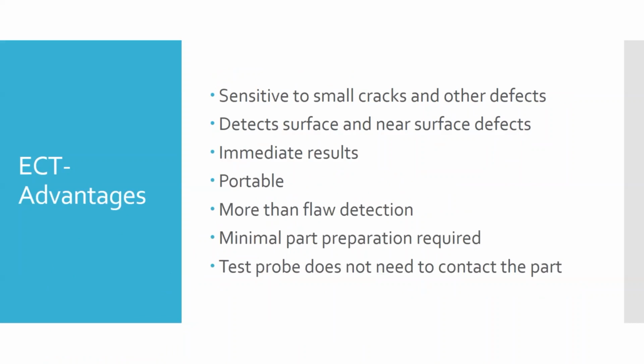It can detect surface and near-surface defects. Liquid penetrant, probably the biggest competitor to eddy current testing, can't find anything subsurface. So if we're looking for not just surface but shallow subsurface defects down to about half an inch, this is the method we can use.